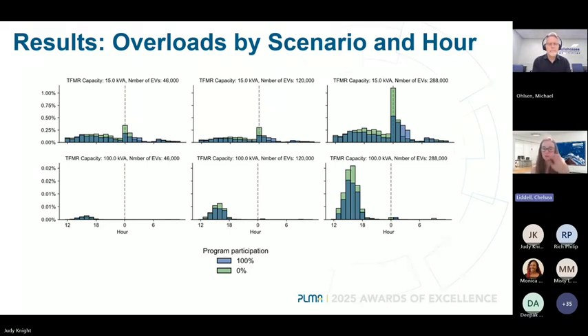And so you can see that during the middle of the day, the program reduced overloads on those smaller transformers. And for that midnight peak, the program really reduced the number of overloads on those smaller transformers. But because the program shifted that midnight peak to later nighttime hours, the later nighttime overloads actually increased a little bit on those really small transformers because they're a lot closer to that capacity value.